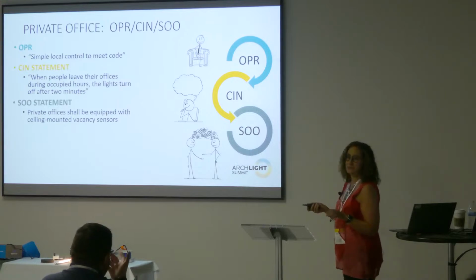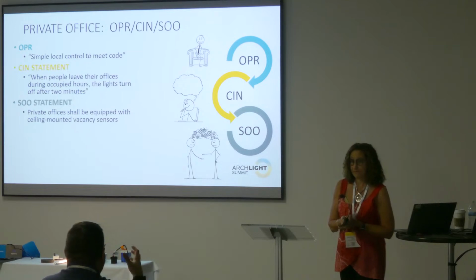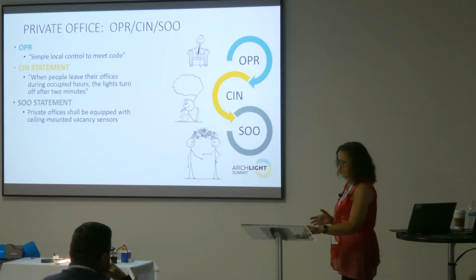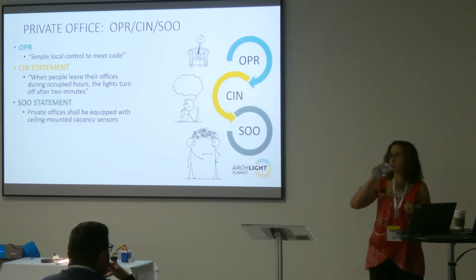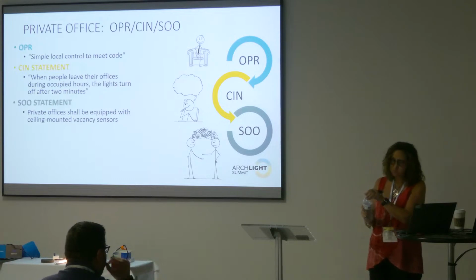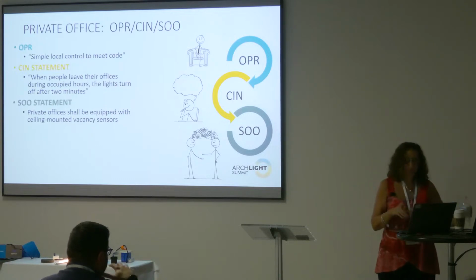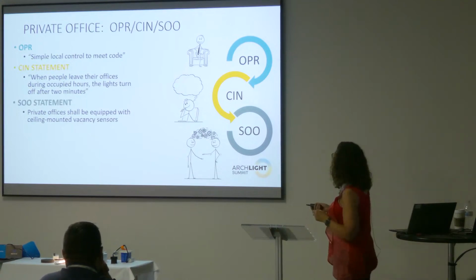I would also add, as far as the ceiling mount versus wall mount goes, you're measuring a 3D space. And you're measuring tangential movement through those for PIR only. So you get a much different reading, somebody walking past one on the far side of the wall away from the sensor, 360 degrees. That is a very, very good point, and thank you for that. All right.